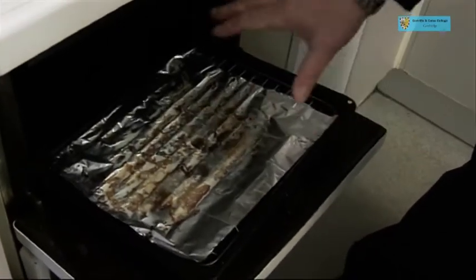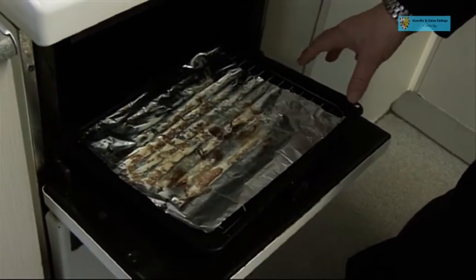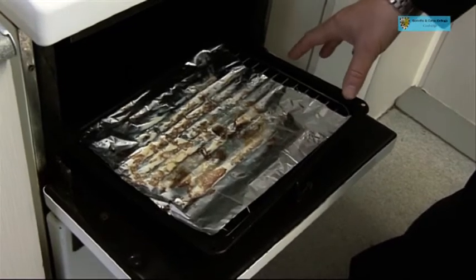But you can see it slowly building up, and we do get sometimes where this is an excessive loading of fat there. And if not cleaned, the fat will build up. If it's left unattended, we will then get a fire occurring. The hygiene is not really the issue. The issue in fire safety is that there is a build-up of a source of fuel, which in this case is fat. And once this fat gets to a significant temperature, it will just spontaneously burst into flame.